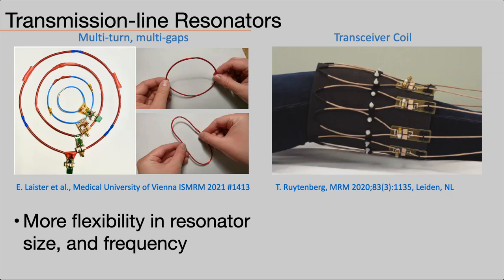So this is a transmit-receive array, not just receive only. This actually doesn't need the coil detuning circuitry because the coil itself is transmitting. So you don't need to have that, but you do need a transmit-receive switch connected to it.